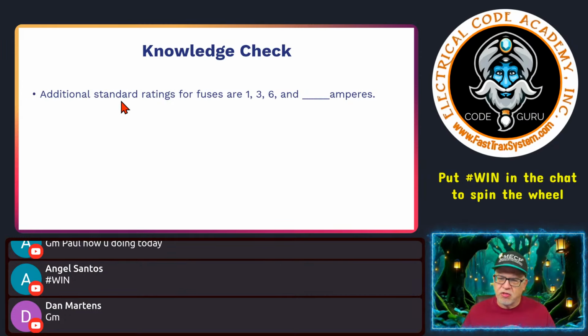It says additional standard ratings for fuses. And notice it says additional, because you have a list of standard fuses, but there are also additional standard ratings for fuses that are 1, 3, 6, and blank amperes. So what is the one that's missing right here? And where do we find this? Well, y'all are familiar. We did it yesterday. Y'all know where in the NEC you go to find the list of standard types of overcurrent protective devices. These are standard. Doesn't mean you can't have a non-standard overcurrent protective device. Sure, they make them. But the list is for the standard type. And usually when the NEC is referencing the standard type, that is where you're going to go. So everybody know where you go?